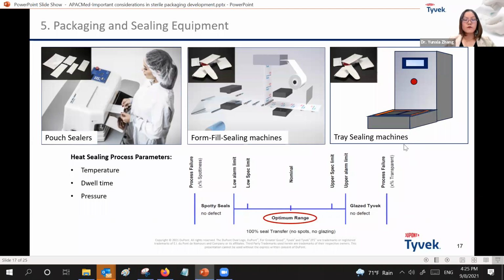So now let's move on to the sealing part. Sealing is very critical as seals are produced in the sealing process. On one hand, seals must be strong enough to withstand the rigors of sterilization, shipping, handling, and storage. But on the other hand, seals should facilitate easy access for the end user to open the sterile packaging using aseptic presentation techniques. So there are three primary heat sealing parameters: temperature, dwell time, and pressure. And these parameters are interactive. A balance between time, temperature, and pressure is needed to achieve the desired seal strength, seal integrity, visual seal transfer, and also the desired opening behavior.